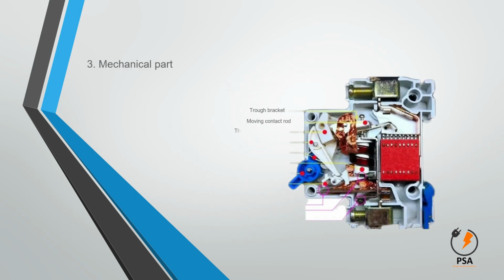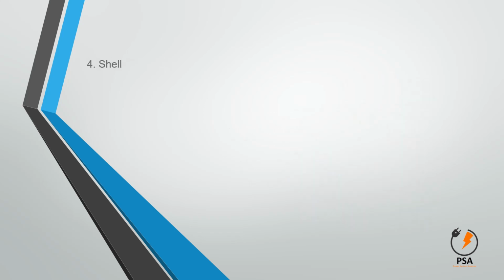Now you can see the mechanical part of an MCB in this photo. The mechanical part supports 2 operations: manual on and off, and automatically performing thermal trip and electromagnetic trip for protection in case of overcurrent or short circuit. It also has a thermal trip current fine-tuning operation. This function is not commonly used.